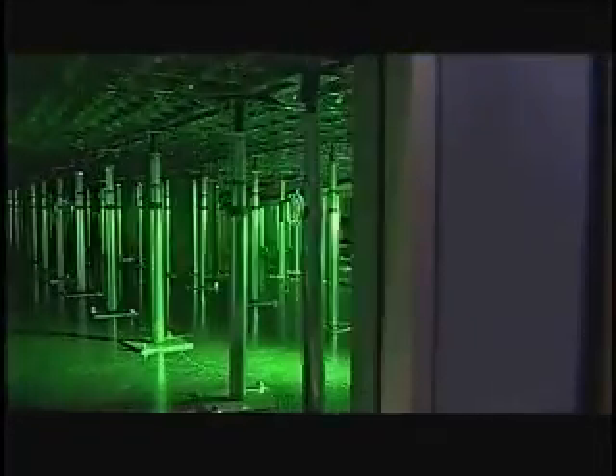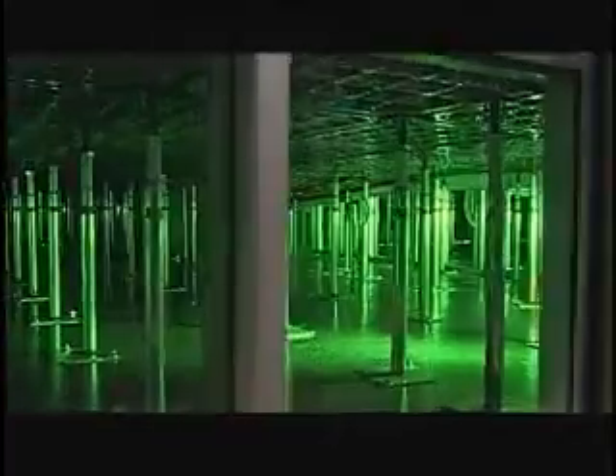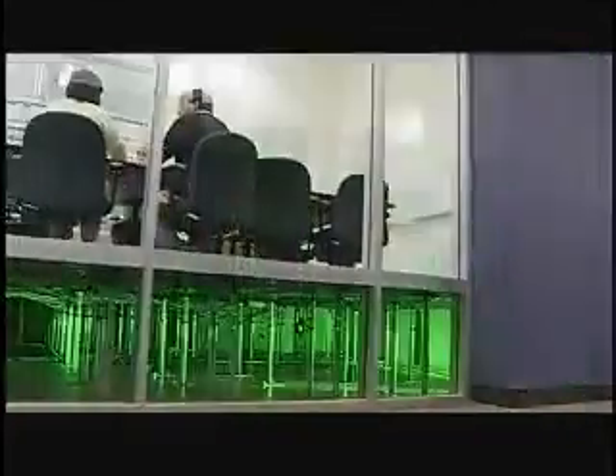We use a 24-inch raised floor to give us plenty of space to move cold air. We move 220,000 cubic feet of air per minute, changing the room air every 45 seconds. We have an N+1 HVAC design, which allows any air conditioning component to fail, and the ranch stays online.